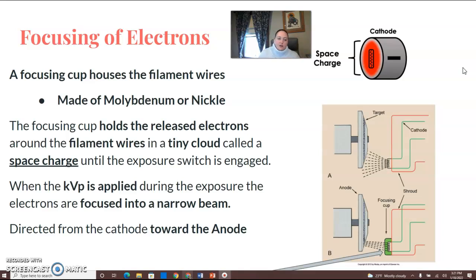When the KV is applied, the electrons move across to the anode side in a focused narrow beam. You can see in the bottom of this picture where the focusing cup is—the electrons go to that focal track on the target, which is our anode. In the top image, the electrons are not in a narrow area, so they're hitting the anode all over the place. The focusing cup focuses the beam toward the anode.